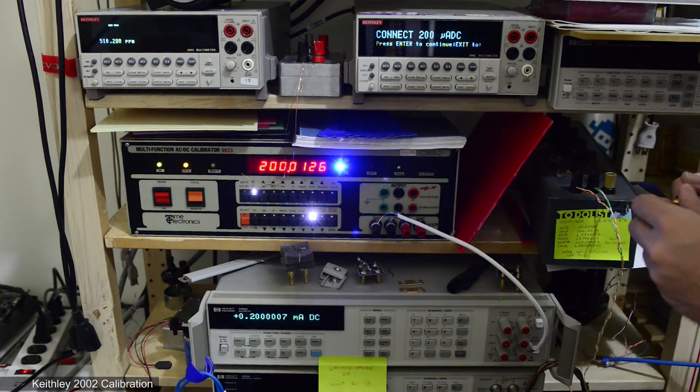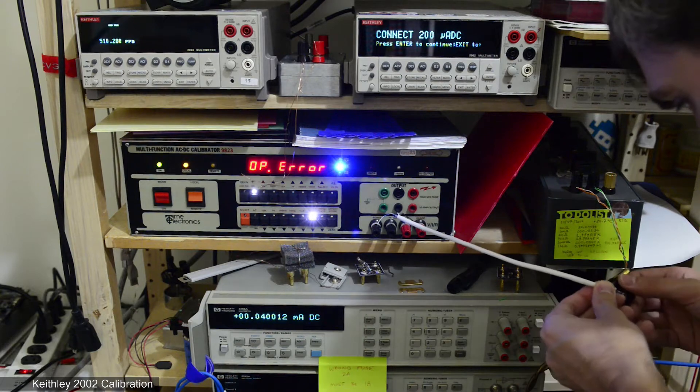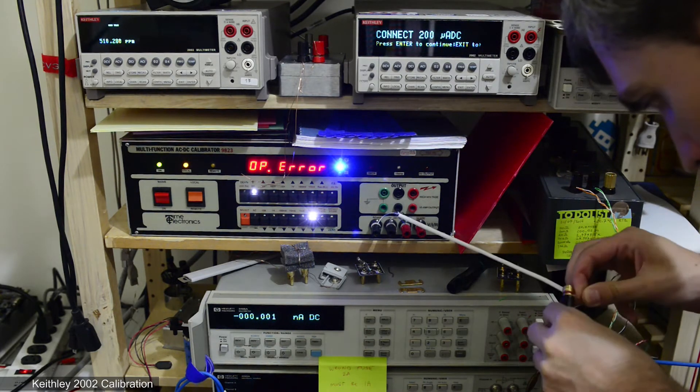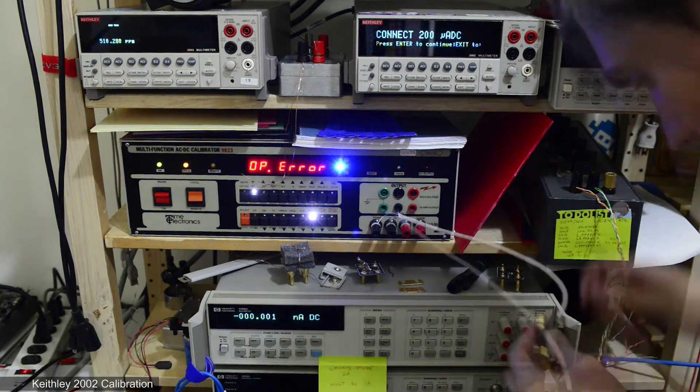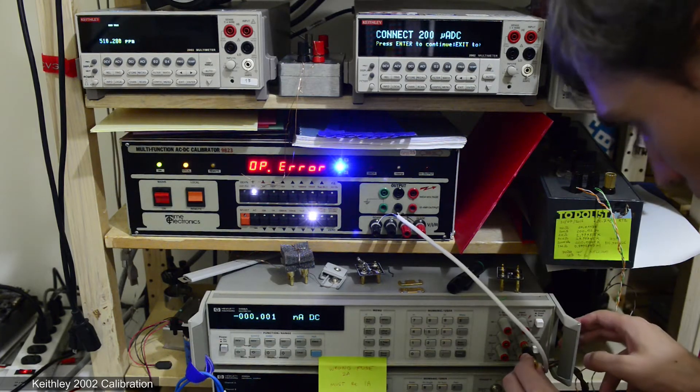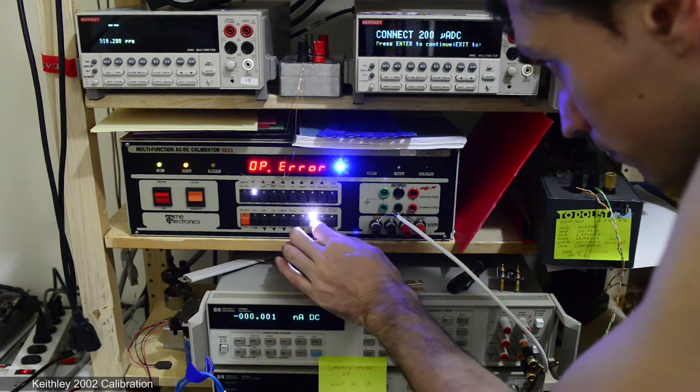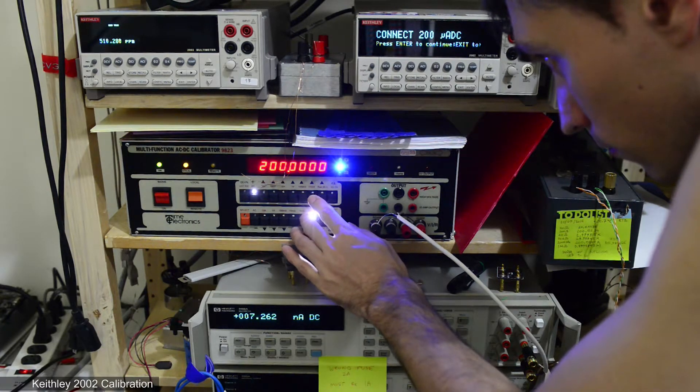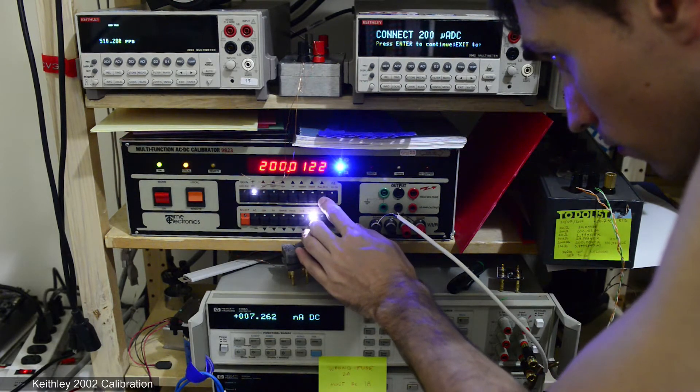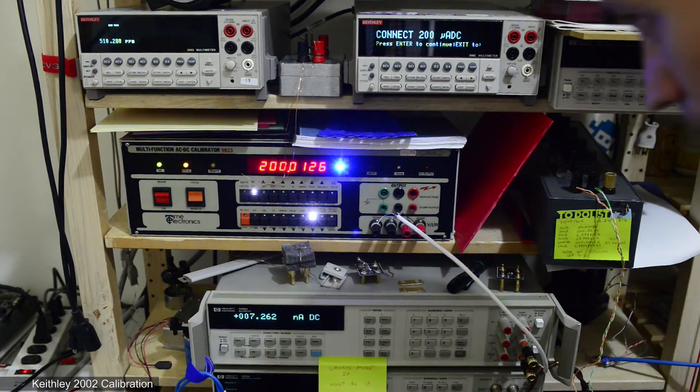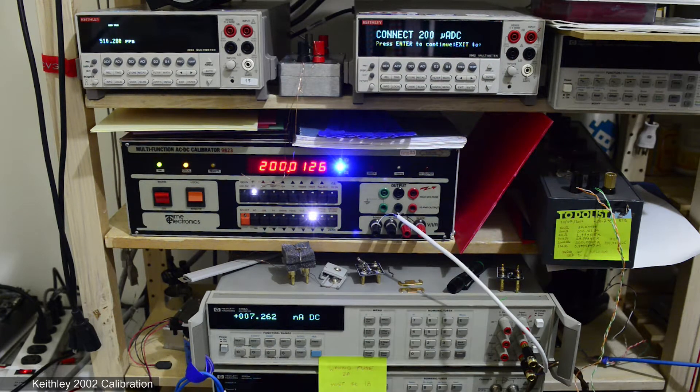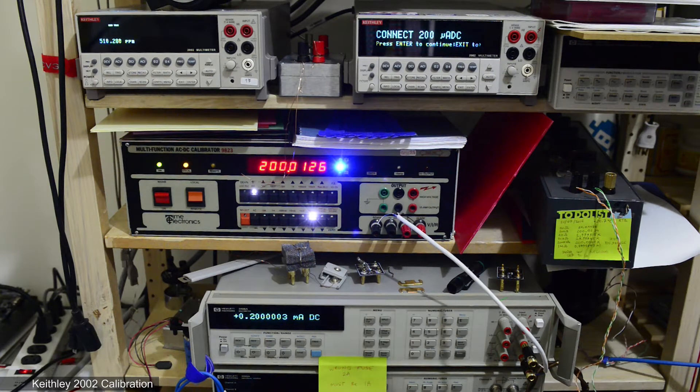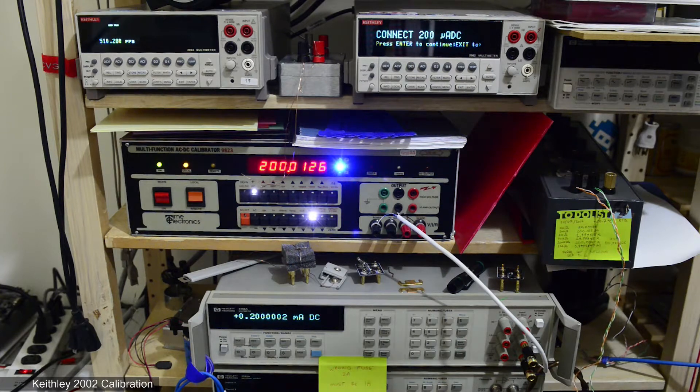Now you can see I connected the calibrator output to the HP meter to measure 200 microamps. So I'll just connect to input current jacks and set 200 microamp range. As you can see HP 3458A has no problem to measure this low current.